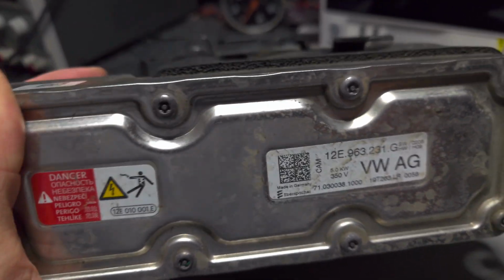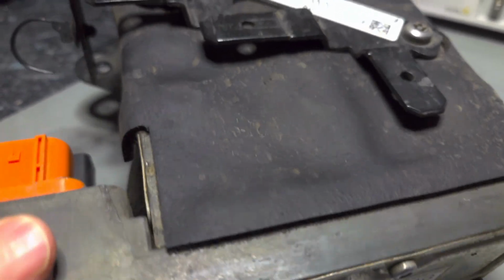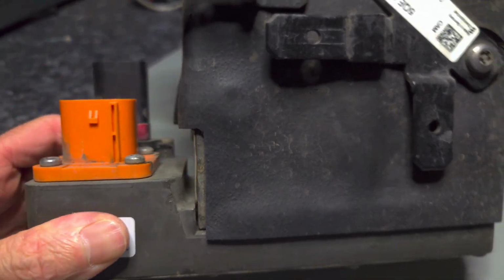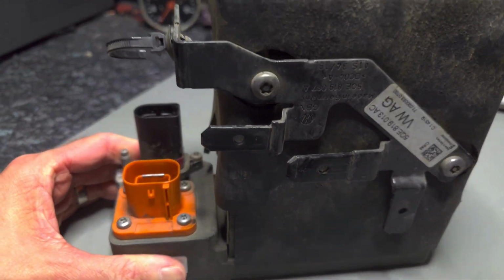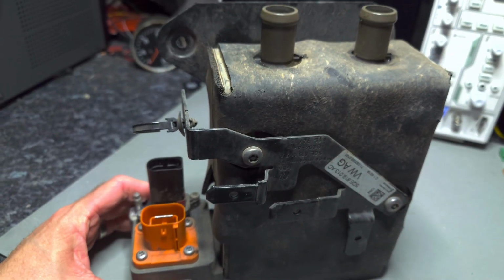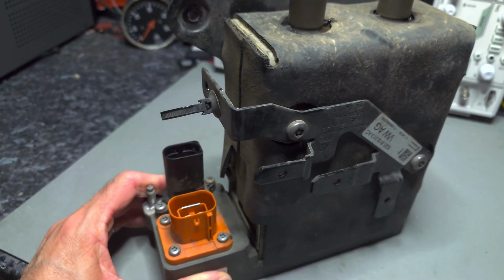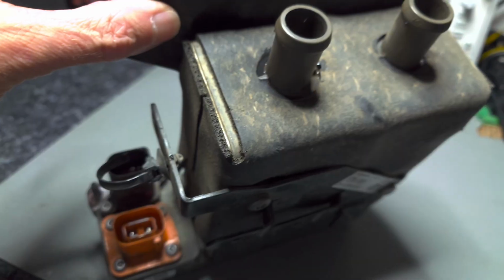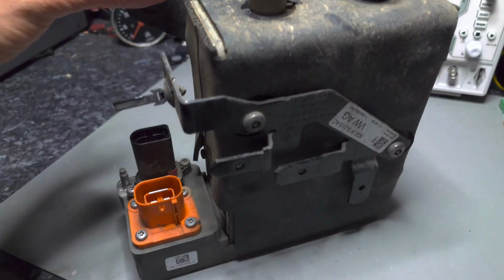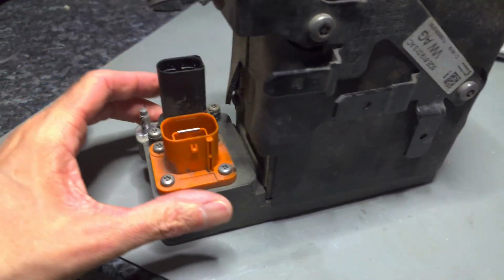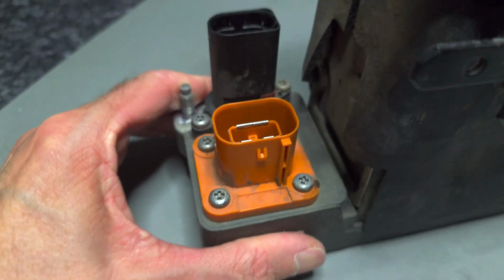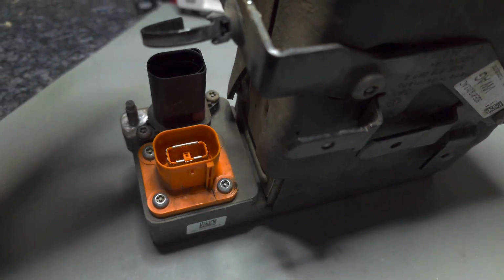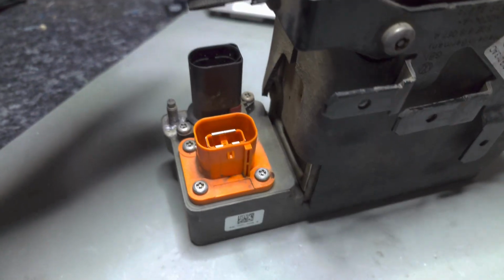I imagine there's more than one heating element in here, so it can switch between different numbers of heating elements to provide different amounts of power. I had originally assumed there would just be one and it would use pulse modulation, but maybe it's not that - maybe it has separate heating elements. Because if it had failed fully on, a 5 kilowatt heater would be significantly lower than 90 ohms.